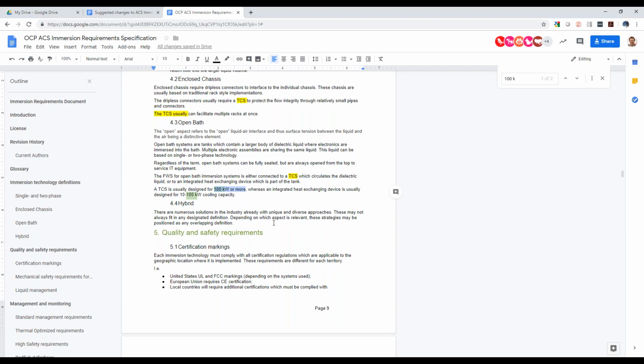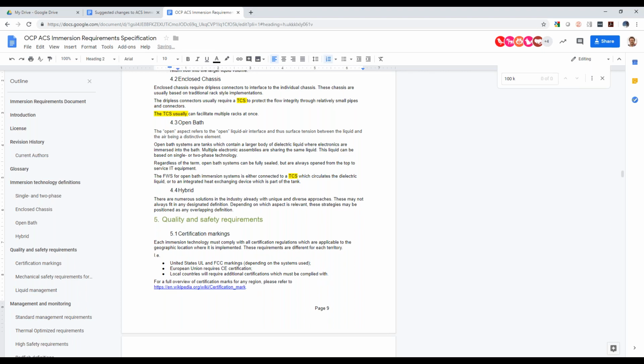The only reason this paragraph is in there is to determine that TCS is usually implemented for larger densities, larger amounts of compute. With a TCS unit, you might just be connecting it to a cold plate, and each cold plate may only have 20 kilowatts of heat. You might connect three racks, meaning your TCS CDU load is only 60 kilowatts. The issue is we're saying it's delineated by 100 kilowatts, but I think a TCS doesn't necessarily start at just 100 kilowatts, it could be lower. I think the amount of questions being raised by the paragraph is already too uncomfortable, so it should be deleted.